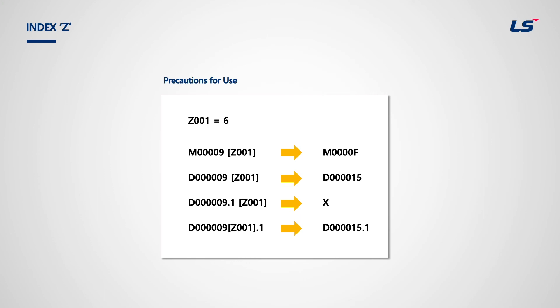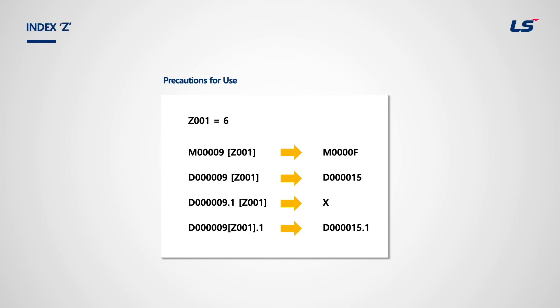For M, Z-index is added as bit, but for D, Z-index is added as word. As explained, the last digit for bit address is expressed in hexadecimal. This is why when Z1 is 6, D9Z1 becomes word D15. However, when index is used with word-based memory used as a bit, it should be expressed as D9Z1.1, not D9.1 Z1. Z-index is used very frequently because it effectively simplifies the ladder program.